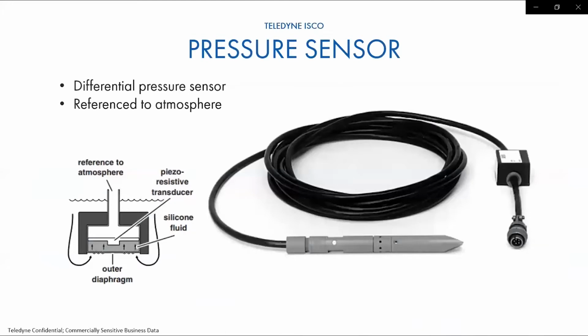Now the pressure transducer, it's a differential pressure sensor. And so what that is, it has a diaphragm on the inside that measures the amount of pressure over the top of the sensor. And they have a reference to atmospheric pressure. So through this cable, there's a vent line that goes all the way up to your flow logger or meter that vents to atmospheric pressure. And the reason that's important is that when your barometric pressure changes, if you did not have reference to atmosphere, you would actually see your levels would increase and decrease as the barometric pressure changes. So it's important to make sure that the line is clear, and then you maintain it by replacing the desiccant on a regular basis or as needed.